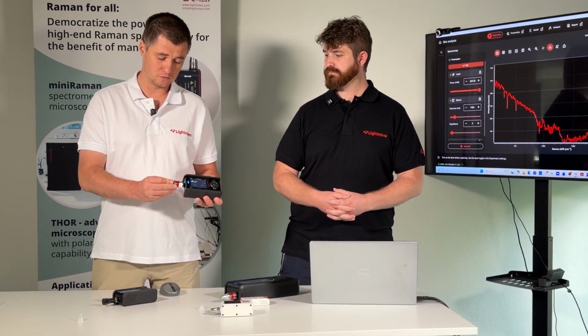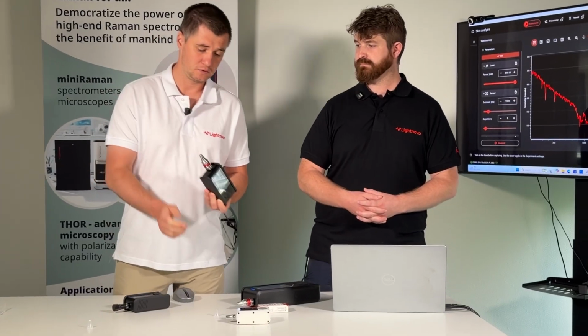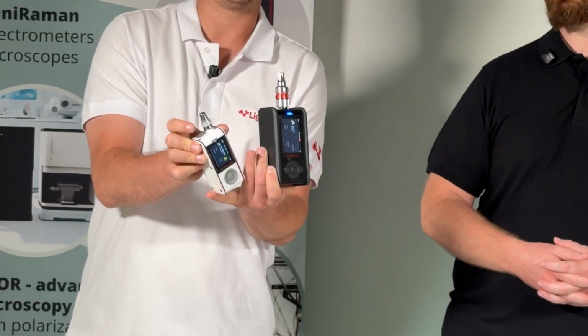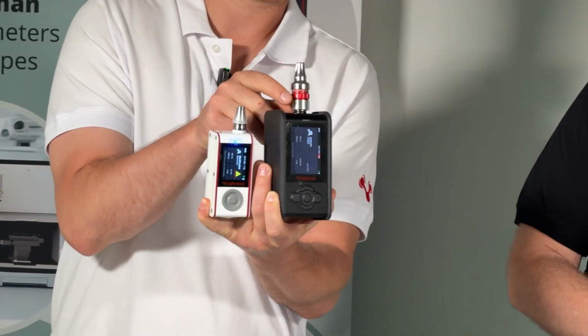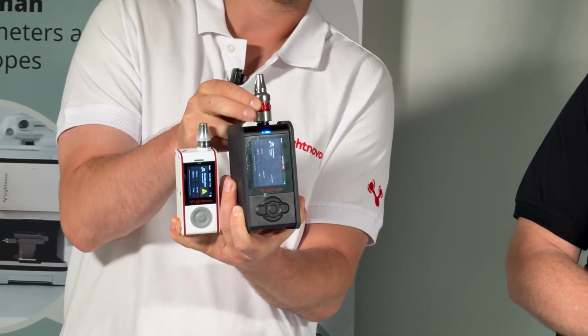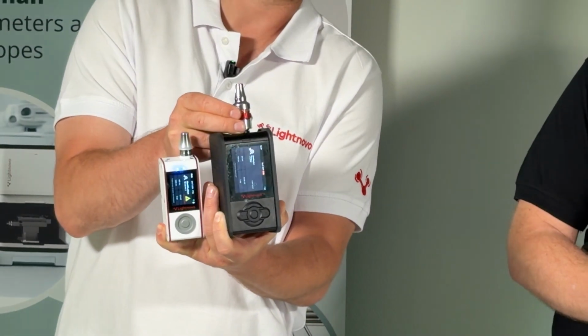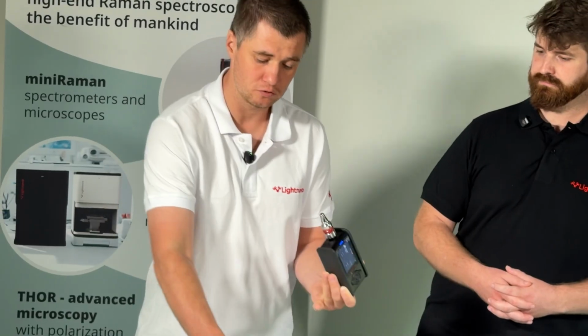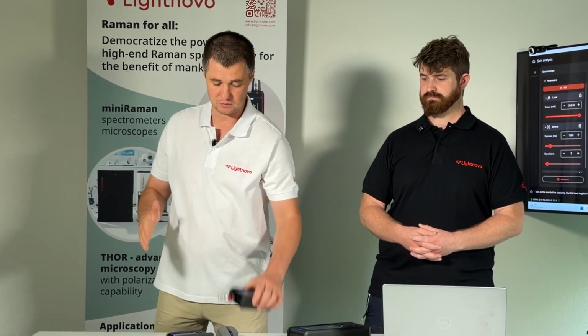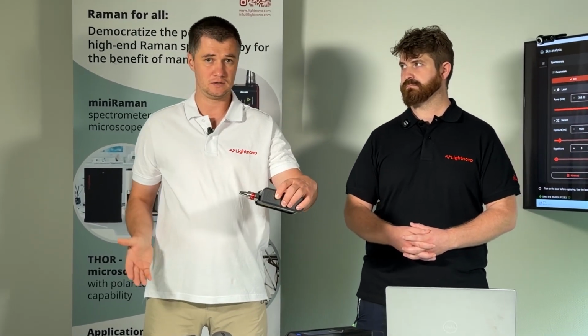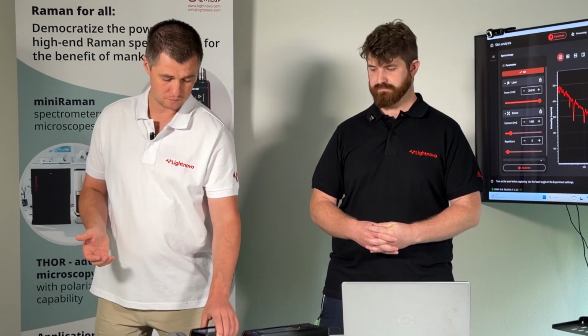But when you attach the probe to the device like that, this probe and another probe, we have two skin probes. One is fixed penetration depth, another is variable penetration depth. You just tune the thread here, and you can go from 0 to 300 microns in depth of the skin. But both of these probes have the same numerical aperture of 0.65, which means that beam divergence is huge, and laser power density drops fast versus distance. That's why after approximately 13 centimeters, of course depending on the maximum power you apply on the device, it's more or less safe for surrounding people and for yourself.